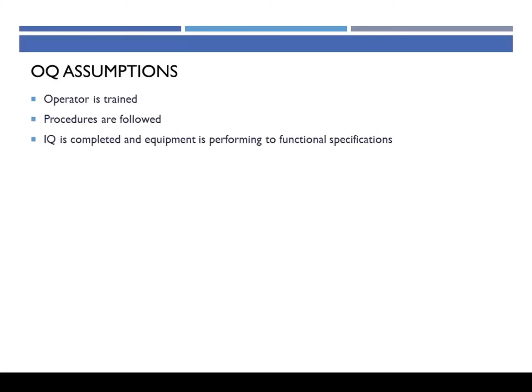So the minimum things we want to get out of our OQ are to make sure we have written procedures that are complete and workable, we've done software validation if necessary, we know what our process inputs or variables are and what the limits for them are, we've optimized our process, we've characterized our process, we know what failures could occur, and we're going to perform worst case studies.